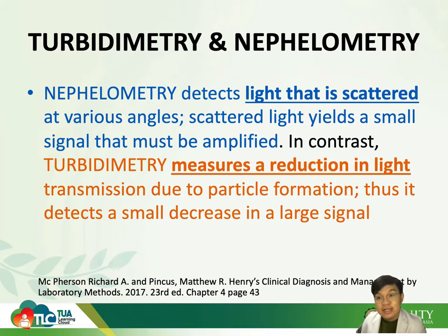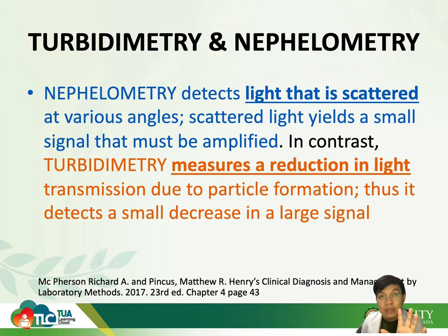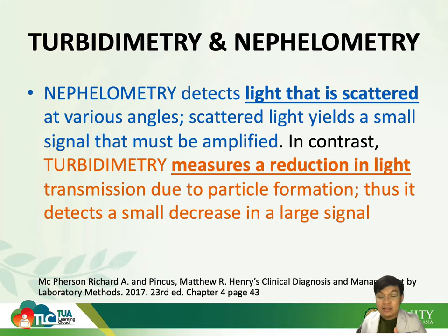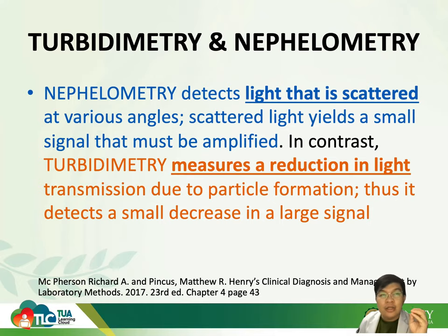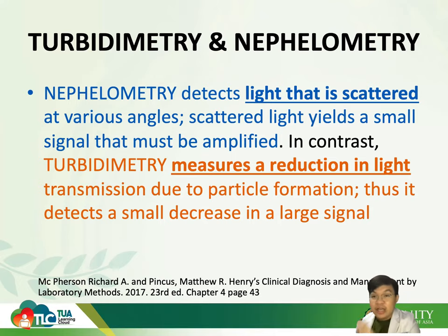In the amplification part, that is now your photodetector — specifically your photomultiplier tube. Remember that in nephelometry, the keyword is light scattered — not just in a linear manner, but at several or various angles. When your light hits a particular molecule, like an antigen-antibody complex, instead of absorbing the light, it would scatter the light in various angles. The more antigen-antibody complexes present in your solution, the more the light will scatter, and the more light scattered, the more you can measure — and that is nephelometry.